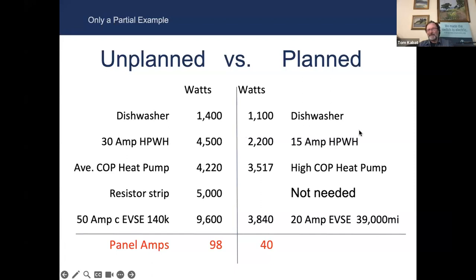It makes sense to look at more power efficient versions, like the 15 amp heat pump water heater. It's got the same compressor as the 30 amp one, but only half the backup heating capability, which is rarely needed if you pick a larger storage tank for your hot water size.